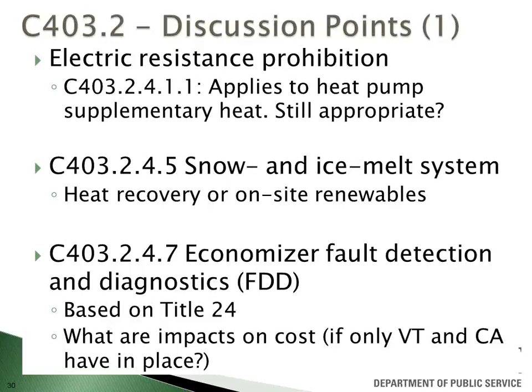So I'll keep moving - economizer fault detection and diagnostics. If you're familiar with mechanical systems and economizing, which is free cooling, it's a great idea and saves a lot of energy. They're often not working right, and the code has been trending towards not only addressing how something is built, but how it's going to operate. So the IECC now has a fault detection and diagnostic section for economizers, which essentially requires certain sensors to be enabled and certain system reports to be pulled so third parties can easily verify whether the economizers are working, because diagnosing that isn't straightforward without paying someone to check everything out.